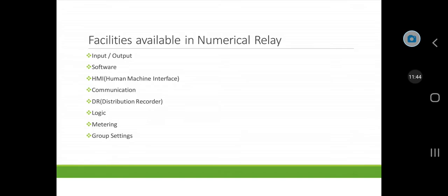The decision taking time by the relay, operating time of the relay, tripping time, carrier send or receive are precisely recorded by the relay. The disturbance recorder is useful in analysis, which can further lead to upgrading of coordination equipment if necessary.